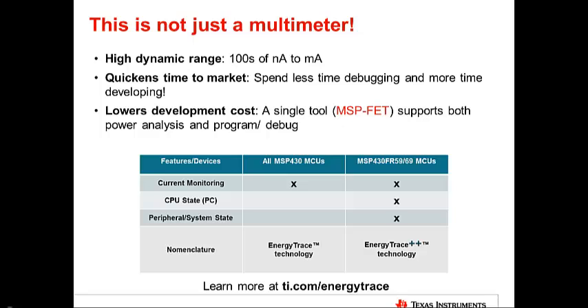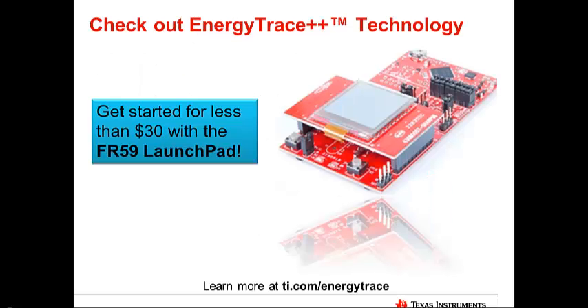When using the MSPFET, our next generation programmer, with any MSP430 device, you will now be able to get real-time current measurement profiles of your application. If you are using select devices, such as those in the FR5 and FR6 series, EnergyTrace++ technology will be enabled, taking power debugging to a whole new level. In addition to the current measurement, EnergyTrace++ technology will offer information on both CPU and peripheral state.